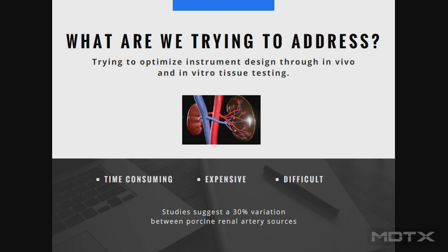So the problem is the tissue. On the tissue side, we have a very noisy data source. And it is time-consuming, and it's expensive, and it's difficult to use, and doing this over and over again requires collection of data that you use statistical methods on in order to determine what the sample sizes are. It gets rather complicated in a hurry, especially if you're looking for very subtle changes in your device. If I change the radius on one of my graspers by 2 millimeters, and my question is, does the mechanical clamping force on this cause damage to the tissue? You may have to clamp on a lot of different tissues and do a lot of different histology before you get to the differentiation between a very small, subtle difference in your device.